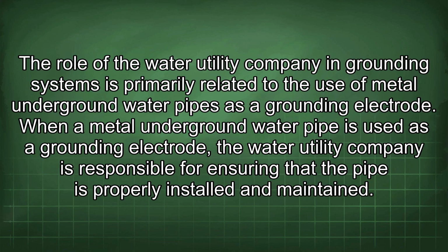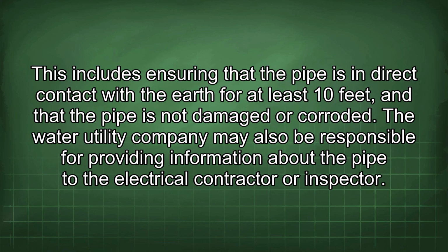The role of the water utility company in grounding systems is primarily related to the use of metal underground water pipes as a grounding electrode. When a metal underground water pipe is used as a grounding electrode, the water utility company is responsible for ensuring that the pipe is properly installed and maintained. This includes ensuring that the pipe is in direct contact with the earth for at least 10 feet and that the pipe is not damaged or corroded. The water utility company may also be responsible for providing information about the pipe to the electrical contractor or inspector.